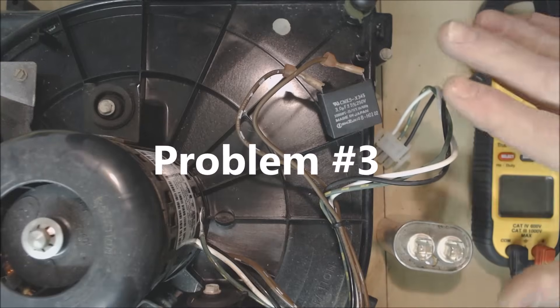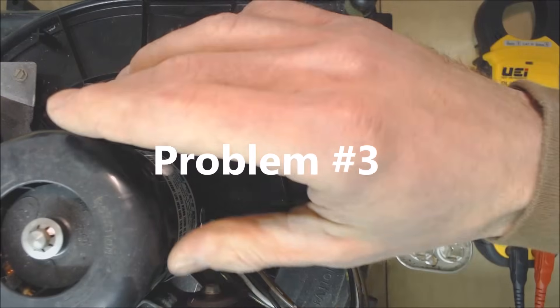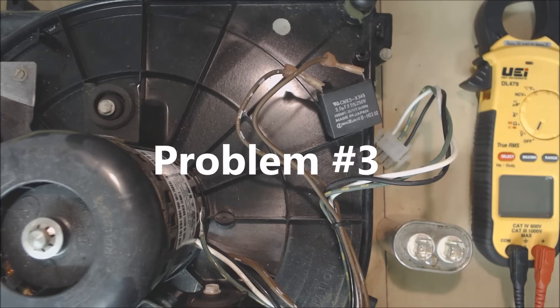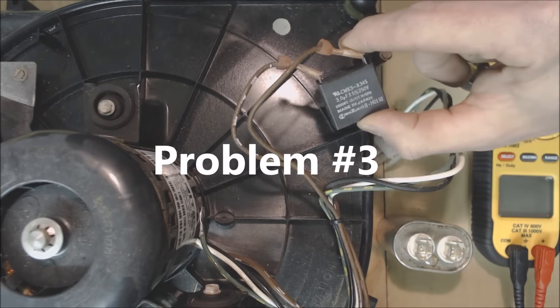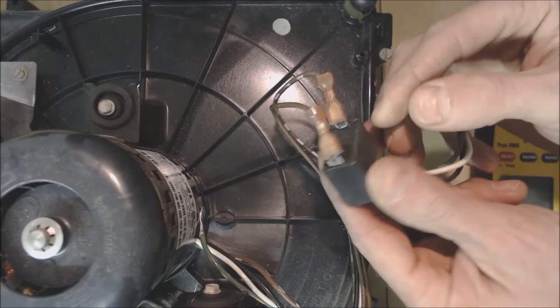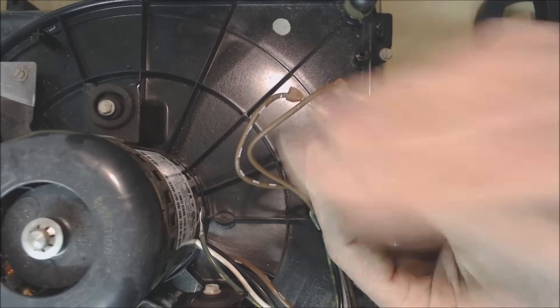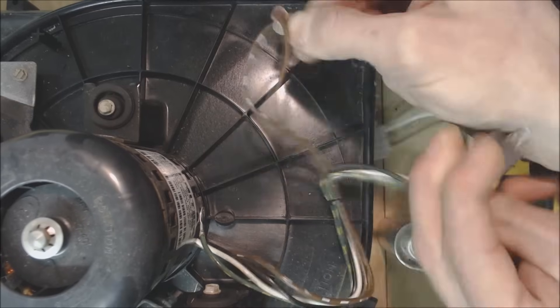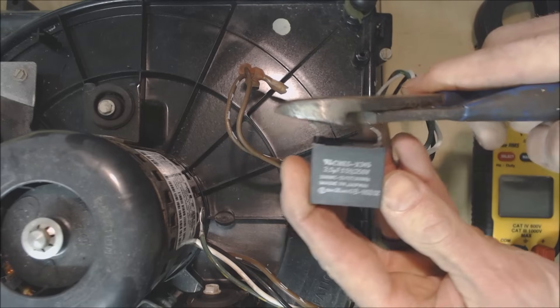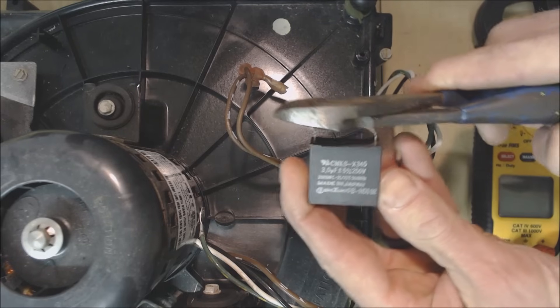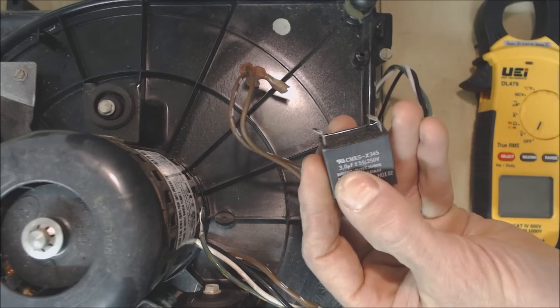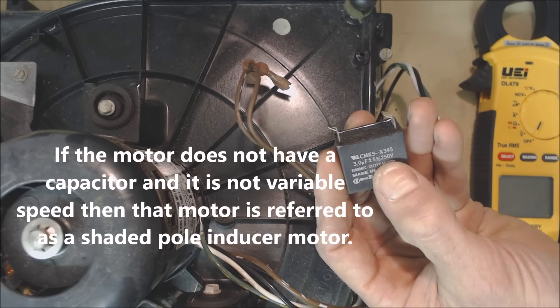Problem number three, what could happen is if you have a 120 volt or 240 volt inducer motor and you have your capacitor could be bad. So this is actually a capacitor this little block right here. So make sure that you have the power off. You're going to go ahead and disconnect the electrical connections off of there. You're going to go ahead and short out the terminals just like this and this one says 3UF and 250 volts.